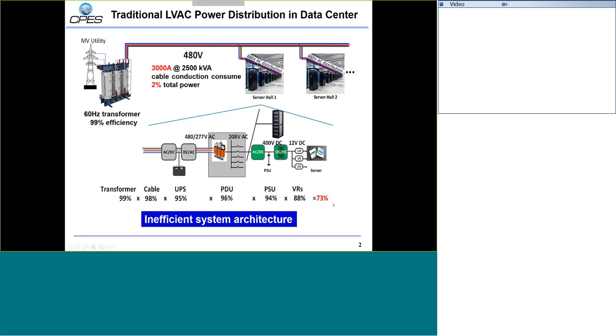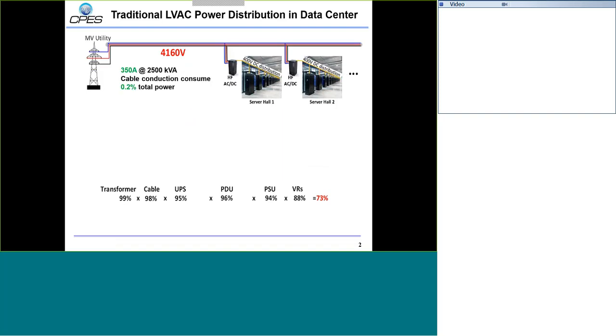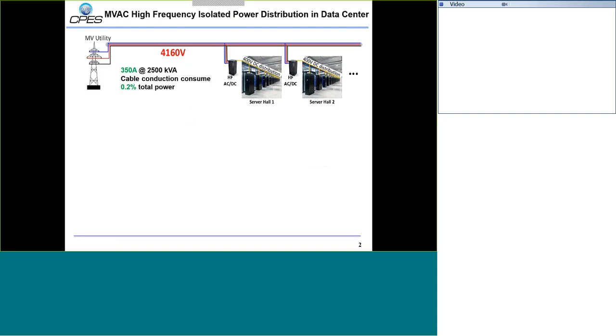So today's system is not very efficient. Our proposed architecture transfers medium-voltage AC directly to the server hall — for example, using 4 kilovolt AC as the distribution voltage. In this way, we can reduce the current on this line and reduce the conduction loss.